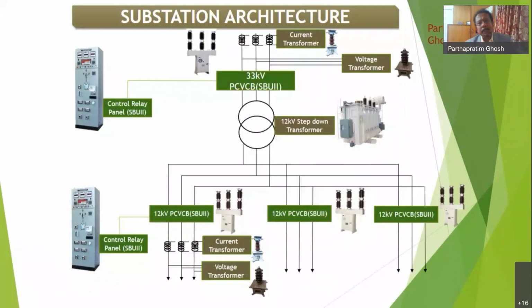This is a typical schematic of a substation architecture, where typically the supply comes through a 33 kV circuit breaker, goes to a transformer, steps down to 12 kV level, and there are typically three 12 kV breakers, and from this breaker it is fed to the next line, rather to the LT segment and to consumers.